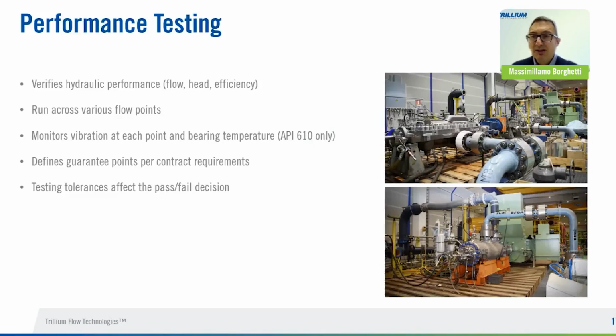Okay, please go. Okay, now we move to the performance testing. That is a critical requirement to verify that the pumps are completely in compliance with the contract requirement. And this testing is absolutely necessary to verify the performance in terms of flow rate, differential head, overall efficiency of the pump, and absorbed power. Generally, we run this test across various flow points, and the scope is to describe the curve in the proper way as much as possible.